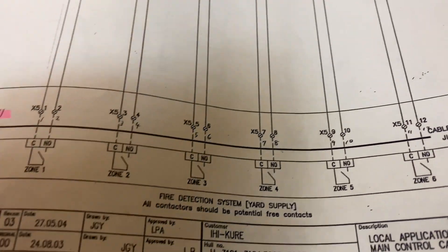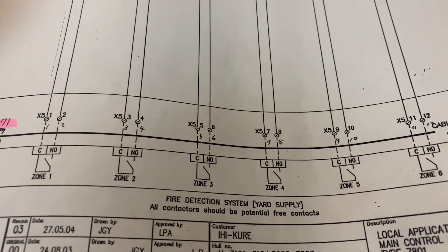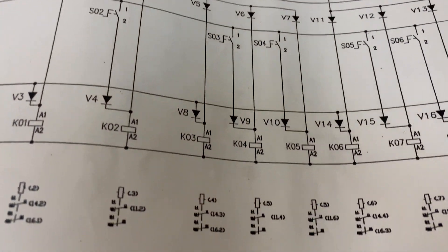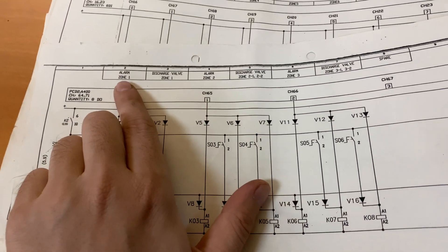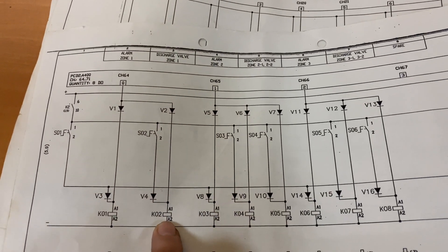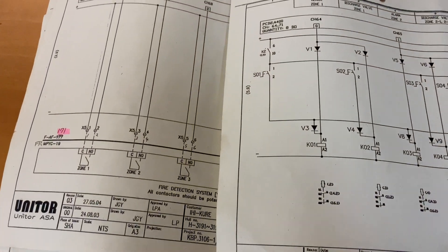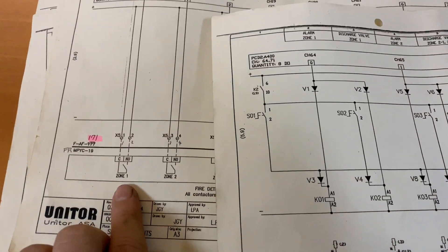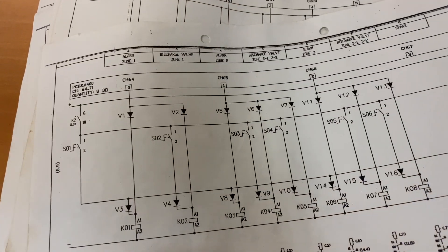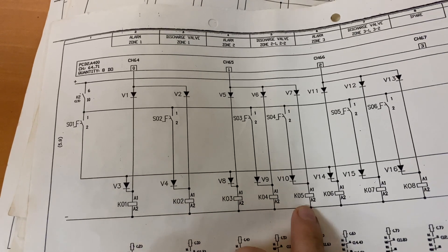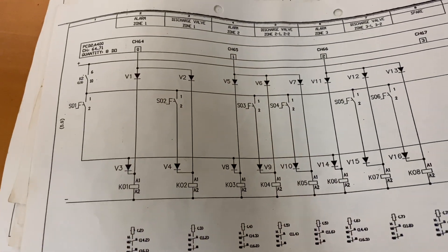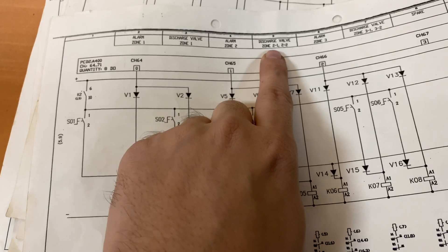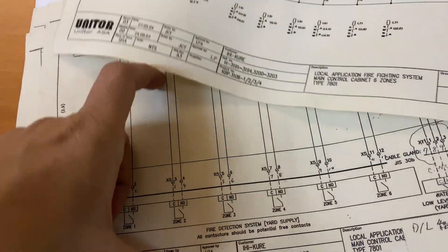What is happening is that every time this relay closes, the valve opens in the wrong area. I checked which relay opens which valve. For zone 1, you would expect the KO2 relay to activate, but based on the actual testing it was not KO2 — the ones activating are KO3, KO4, and KO5. So the channeling from the output of the PCD2 is not correct, but it is the correct discharge valve.